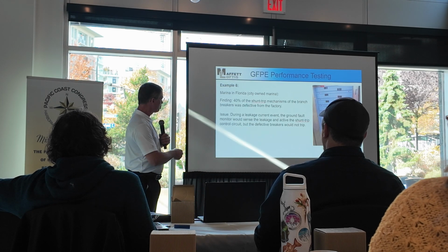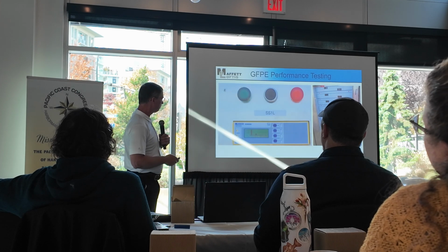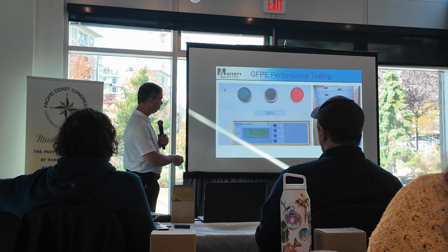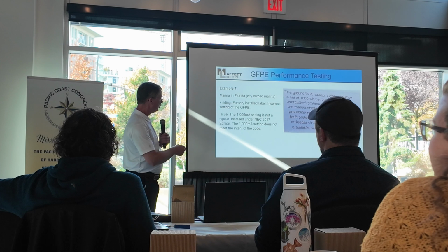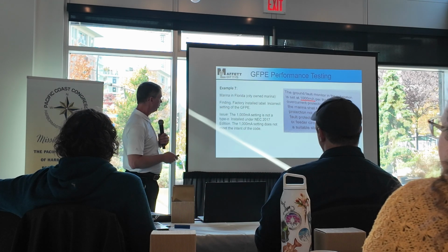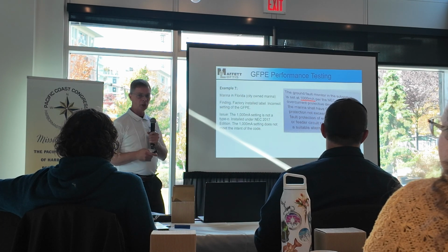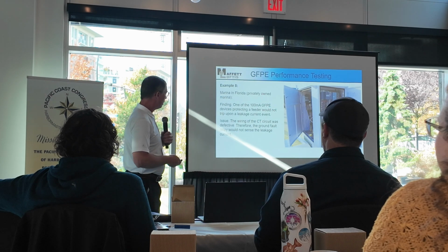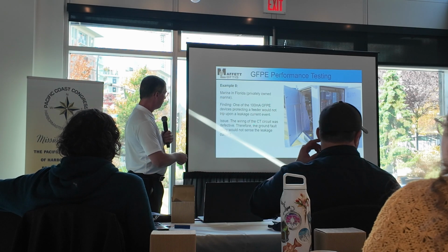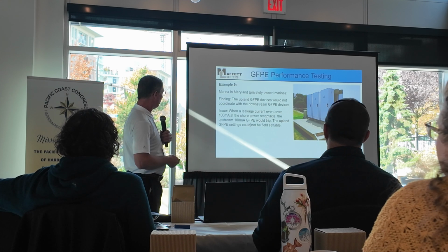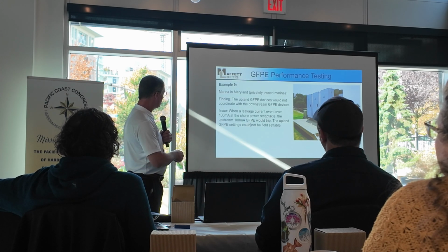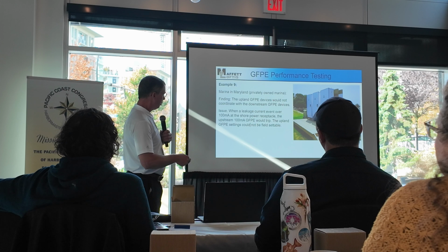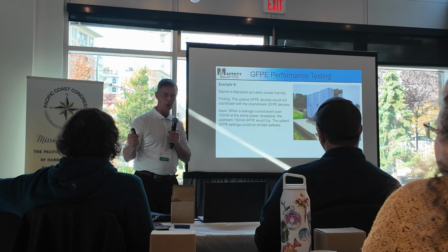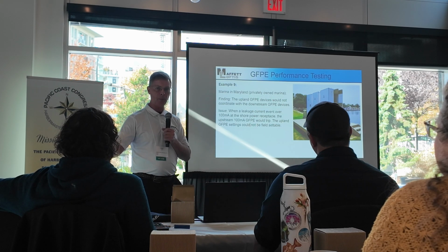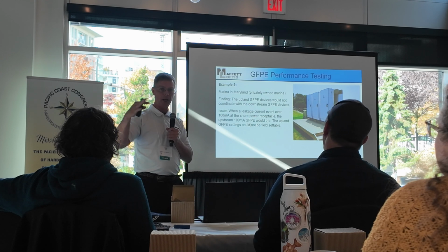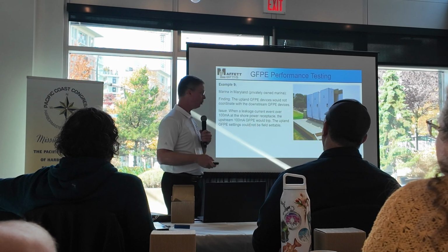Here's another one where 40% of the shunt trip mechanisms failed. And then no matter how much leakage current I would pull, it wouldn't work. Here, 1,000 milliamps doesn't work very well. Code just says 100 milliamps. Here's another one where the CT circuit was defective and wouldn't trip the breaker. Here's another one where the leakage current wasn't coordinated, so I could put in about 120 milliamps on the 30 milliamp, and it always tripped the 100 milliamp upstream and knocked out multiple boats at one time. So we had to make adjustments to that.